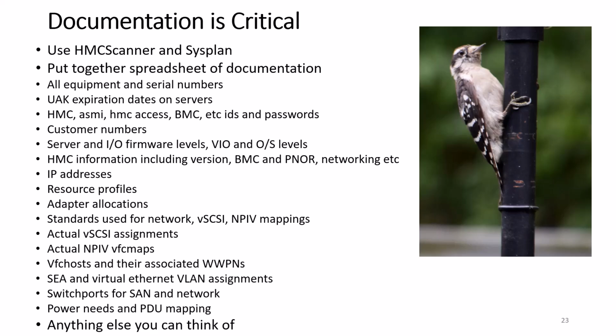One of the other things you need to pay attention to that people don't is power needs and PDU mapping. One of the things that frustrates people is that you have to have more power available than you would actually use, and that's because of how redundancy works. So if you've got 30 amp PDUs, you can only use 4.98 kVA by electrical regulations on a 30 amp PDU - they basically let you use 24 of the amps. So you have to calculate how much amperage you actually need.